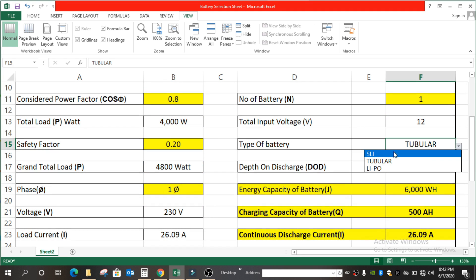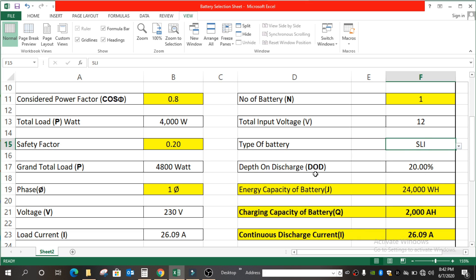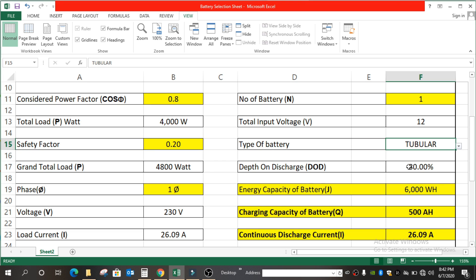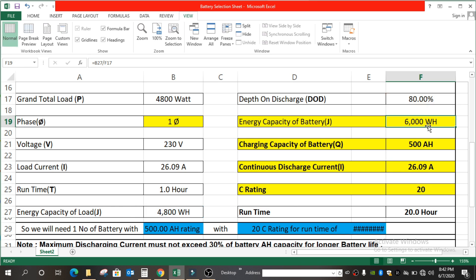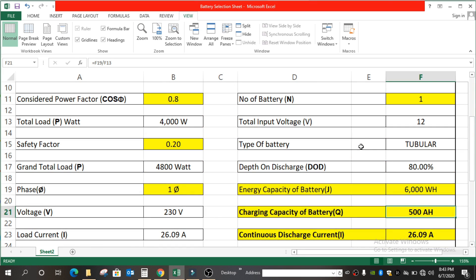Then type of battery — whether tubular or SLI. If you select SLI, the depth of discharge goes to 20%, but since we have considered tubular, it goes to 80%. Then the energy capacity of battery, which is B27 divided by F17 — that is energy capacity of load divided by depth of discharge. So we get 6,000 Watt-hours as the energy capacity of our battery. Then the charge capacity equals F19 divided by F13 — energy capacity of battery divided by input voltage.